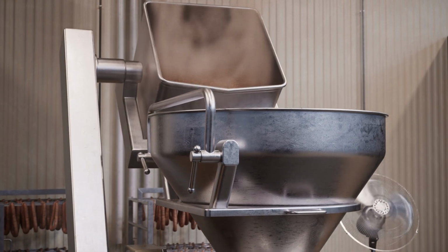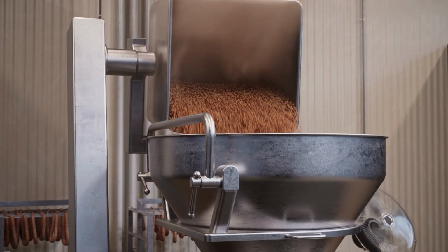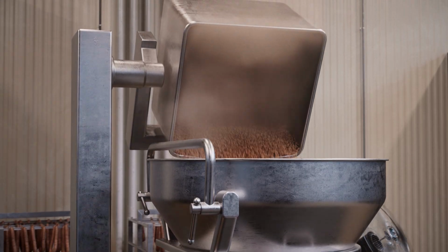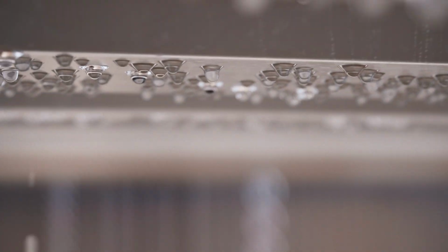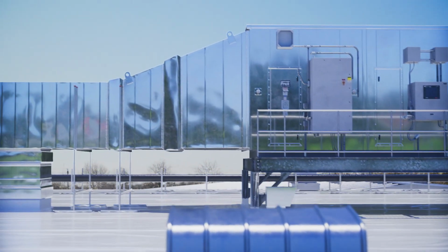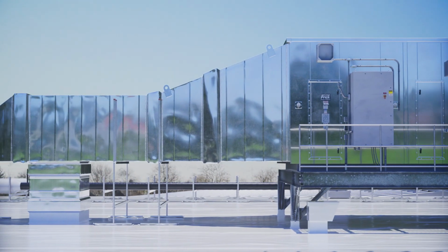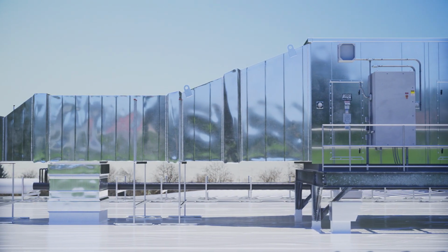Condensation can also occur when moisture is produced in the room by equipment or open product cooling. The moisture evaporated from the product or released by the process raises the room's relative humidity, thus creating vapor that is prone to condense. If the problem is caused by open product cooling, then dehumidifying the room with a desiccant dryer or ventilation with outside air may solve the problem.